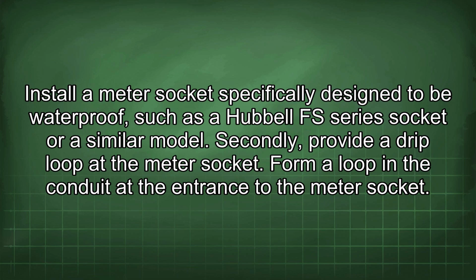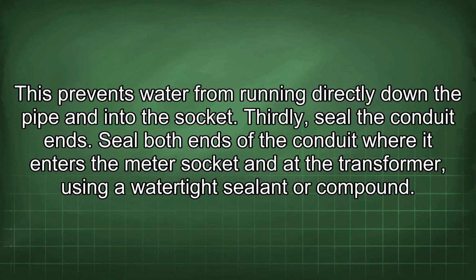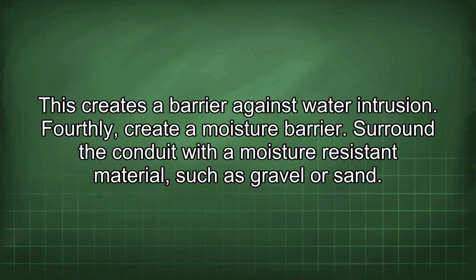Secondly, provide a drip loop at the meter socket. Form a loop in the conduit at the entrance to the meter socket. This prevents water from running directly down the pipe and into the socket. Thirdly, seal the conduit ends. Seal both ends of the conduit where it enters the meter socket and at the transformer, using a watertight sealant or compound. This creates a barrier against water intrusion.